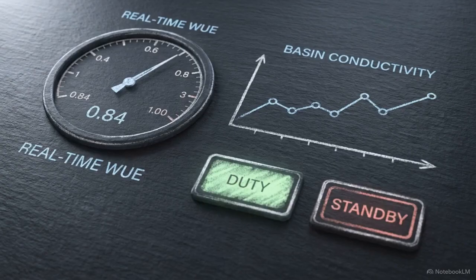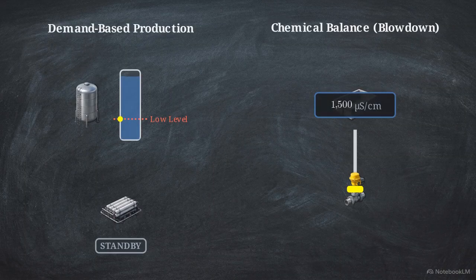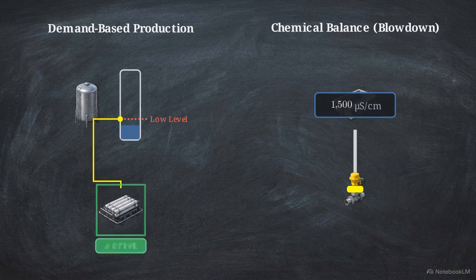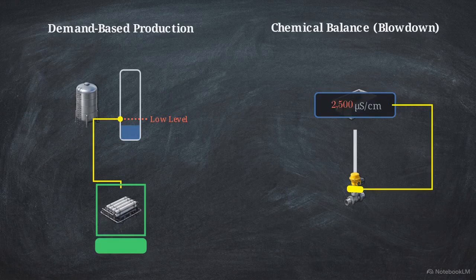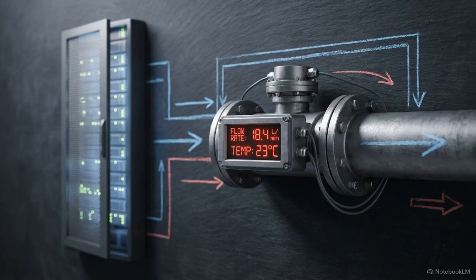Managing this multi-domain infrastructure requires integrated control logic. This dashboard displays the monitoring baseline, real-time WUE, basin conductivity, and SWRO train status. The loops are highly dependent. A drop in the storage tank automatically fires a standby SWRO train, while high conductivity in the tower basin triggers blowdown valves to maintain chemical balance. Accurate WUE reporting is only possible if the system can explicitly measure and control every drop of water across this logic chain.